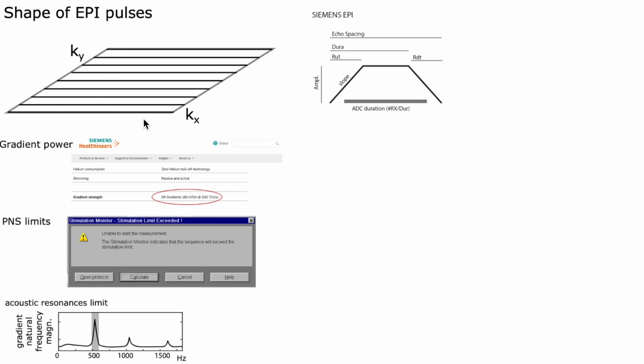So by going through k-space, switching the gradient back off and on and off and on again at a certain frequency means that you put a lot of energy into the system and it can start to vibrate. A lot of energy that you put into the gradients at a certain frequency builds up, it shakes more and more, becomes very, very loud, and the eddy currents are pretty bad, which are a huge challenge for the low bandwidth that we usually have in layer-dependent fMRI.